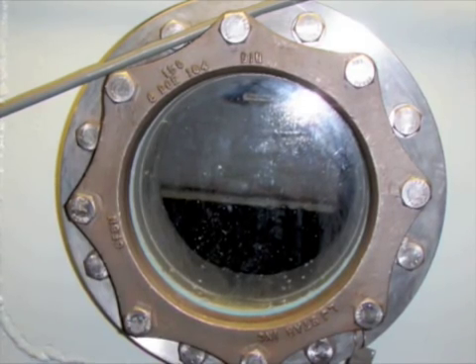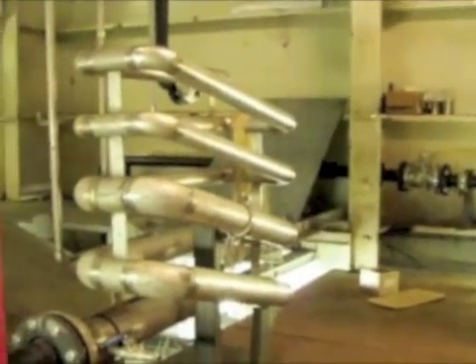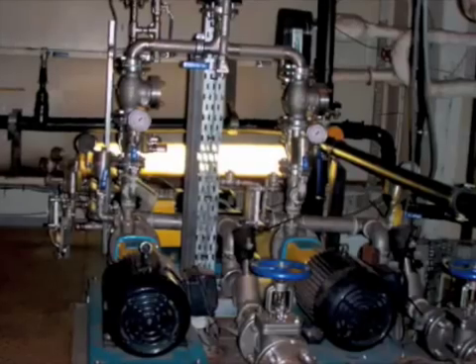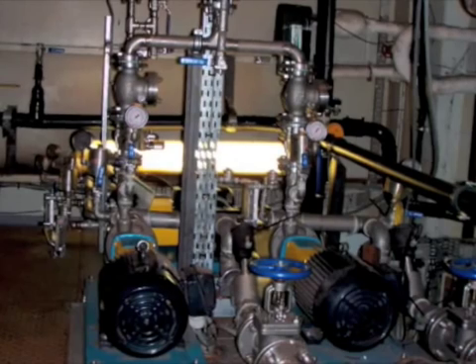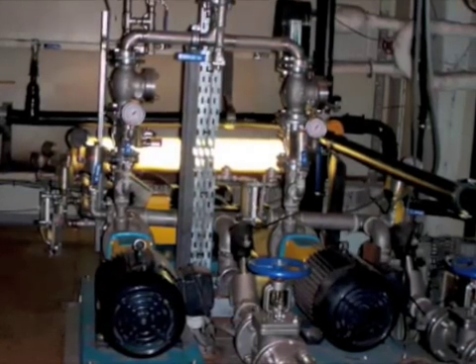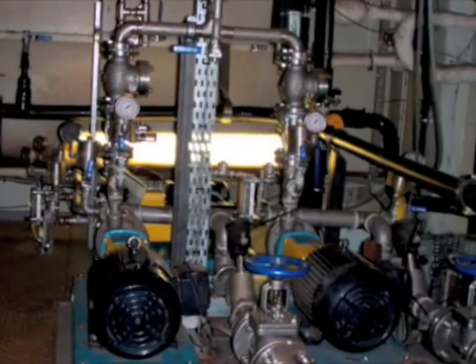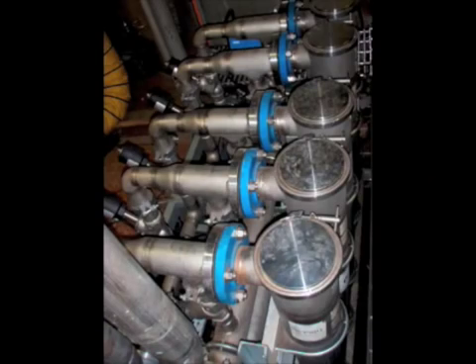At this point, a small amount of flocculant chemical and air is added to the water in order to float solids out of the water. The water is cleaned down to approximately 150 parts per million suspended solids. At that point, it is pumped from the hydraulic separator through 5-micron filters and on to the tubular ceramic filters.